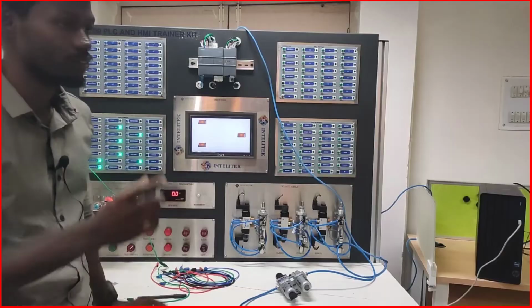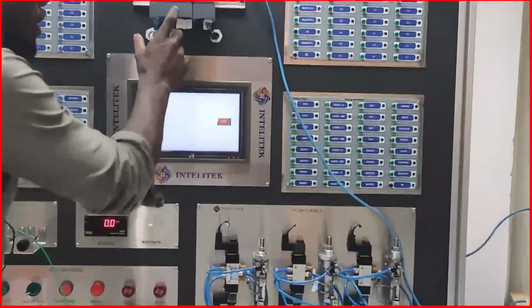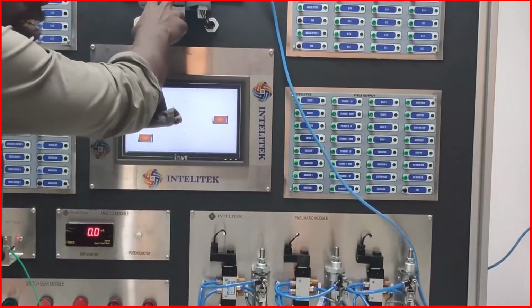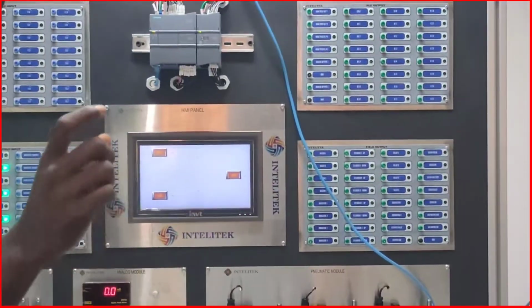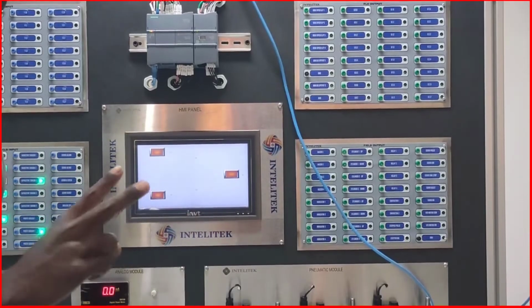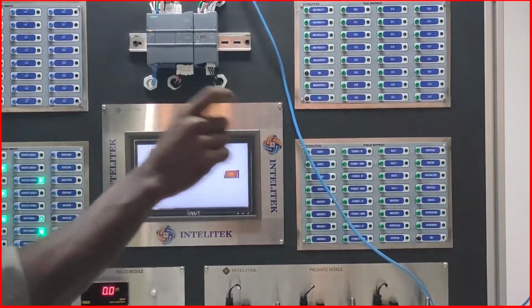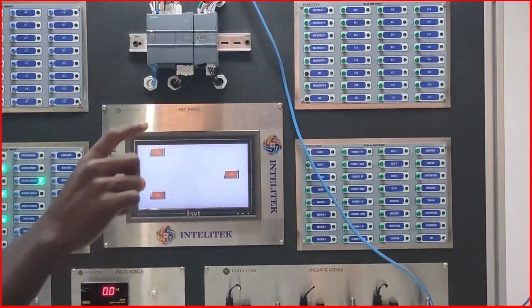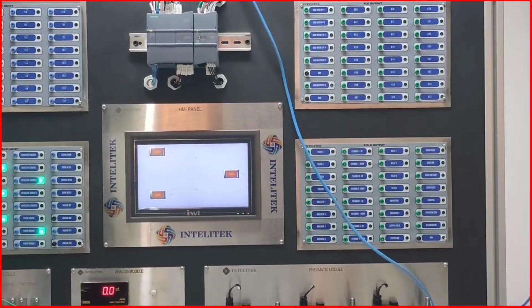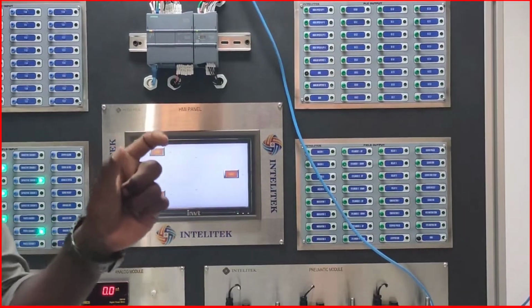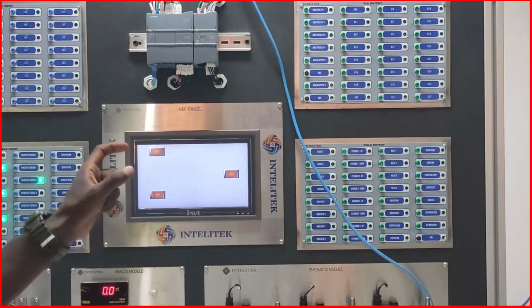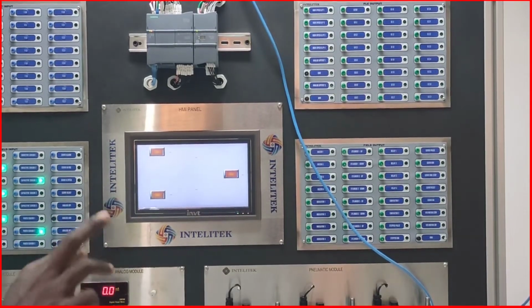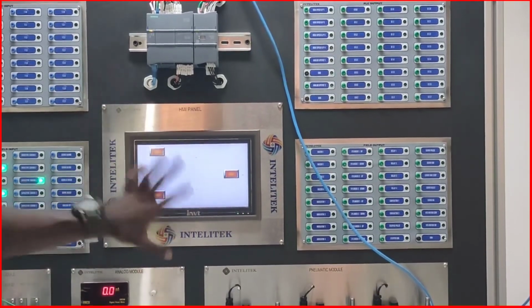For connecting this HMI, the IP address of this PLC and this HMI should match. We have to check both HMI IP addresses and enter them in the HMI software. Only then will it be connected. Otherwise, if there's a port number, that port number and IP address should match; if anything mismatches, it will not get interfaced.